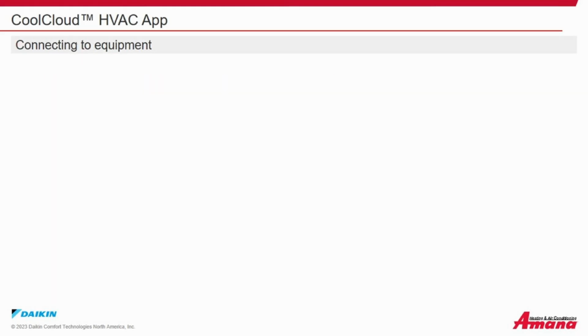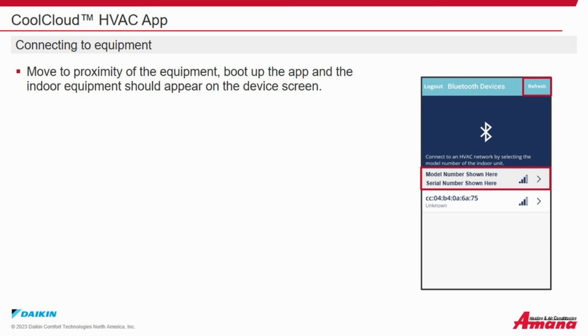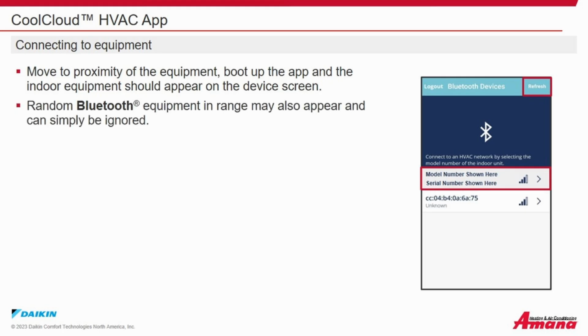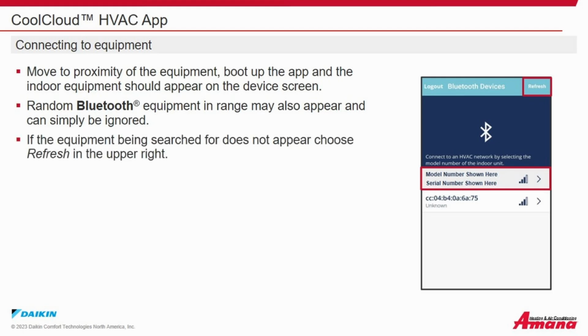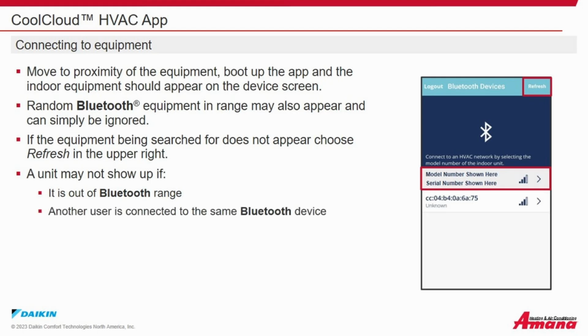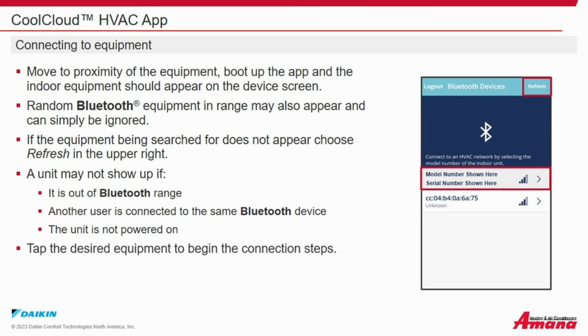Connecting to equipment. Move to the proximity of the equipment, boot up the app, and the indoor equipment should appear on the device screen. Random Bluetooth equipment in range may also appear and can simply be ignored. If the equipment being searched for does not appear, choose Refresh in the upper right-hand corner. A unit may not show up if it is out of Bluetooth range, if another user is connected to the same Bluetooth device, or if the unit is not powered on. Tap the desired equipment to begin the connection steps. Pressing Logout returns the user to the previous login screen.